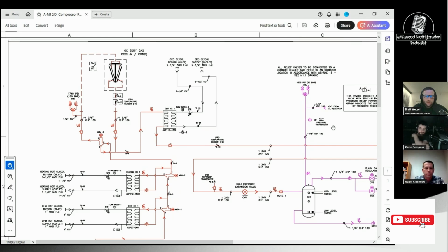I was going to say, you could do the TD of the gas cooler, right? Essentially, if the gas cooler has a 6 degree TD on there, once it hits 80 degrees, it's going to try to maintain 86 degrees, which is right under transcritical. So after that, you really want the fans running 100% anyway. Exactly. And so it doesn't really matter at that point. What does it matter if the fans are running 100%? At that point, it's just a de-superheater. And then have some sort of lower pressure as far as the fast recovery, in case you have some kind of drastic load automatically pop up.